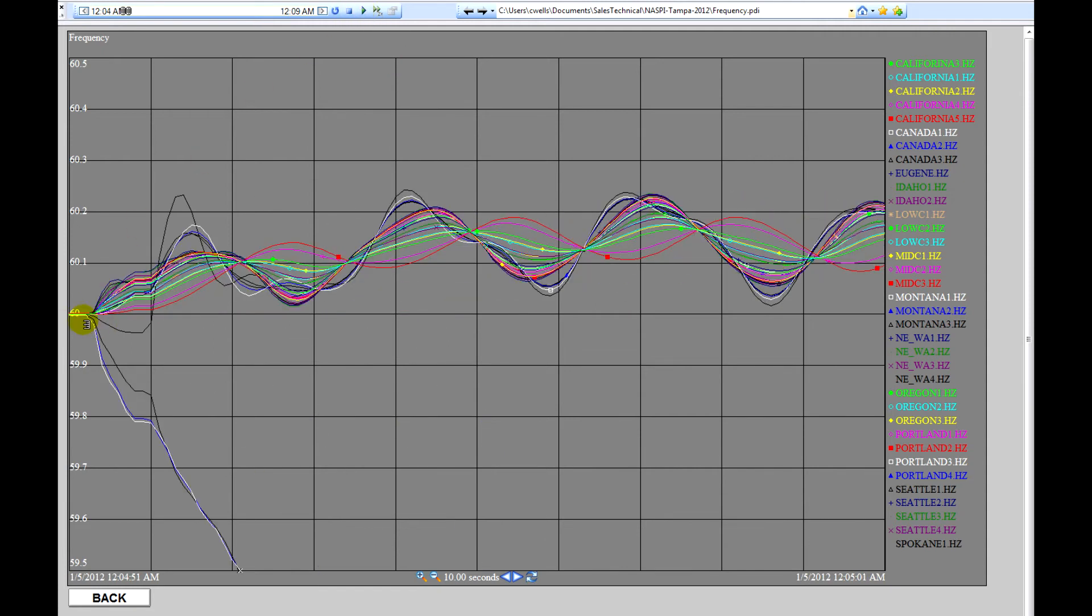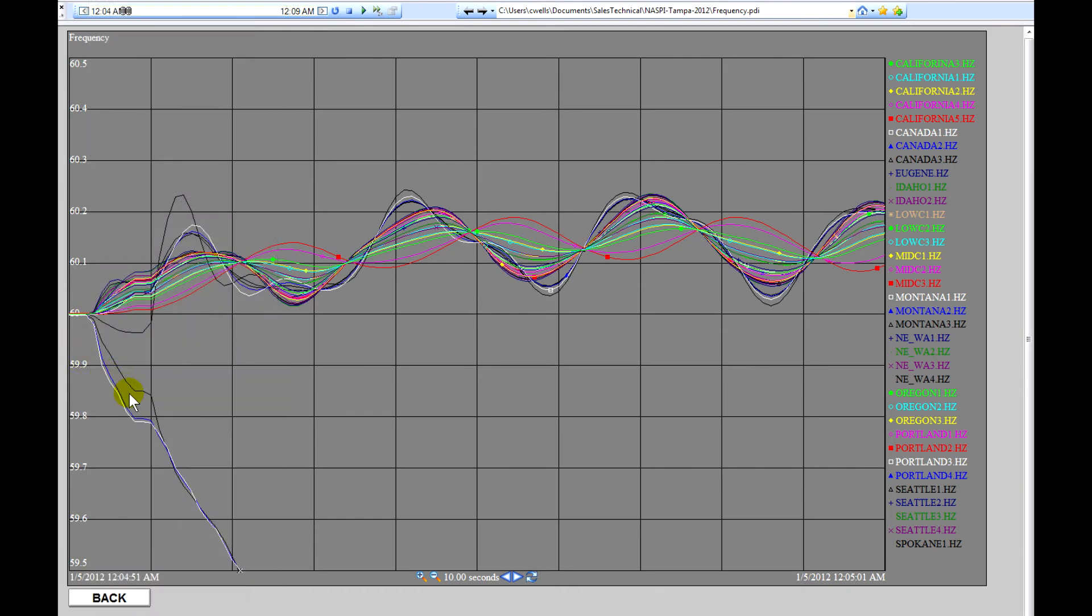We'll see this is where the separation occurred. The frequencies were around 60. All the systems in Canada decayed in frequency. The frequency throughout the U.S. increased.